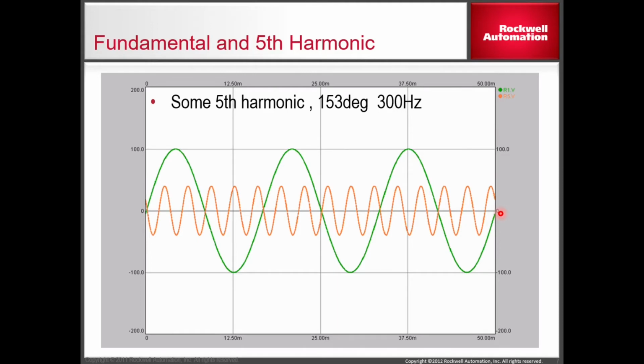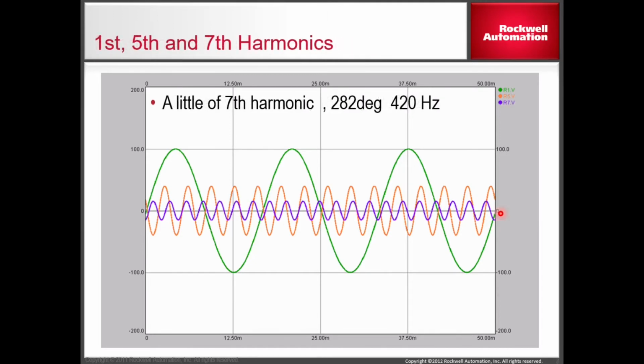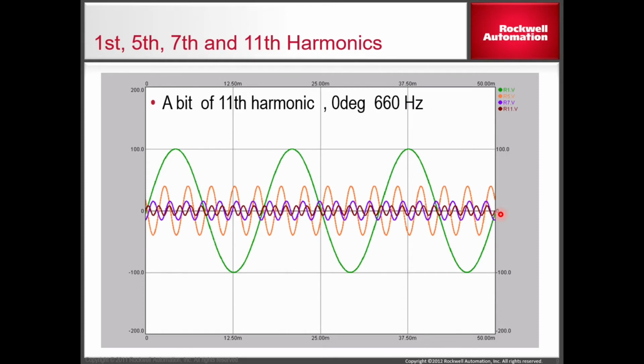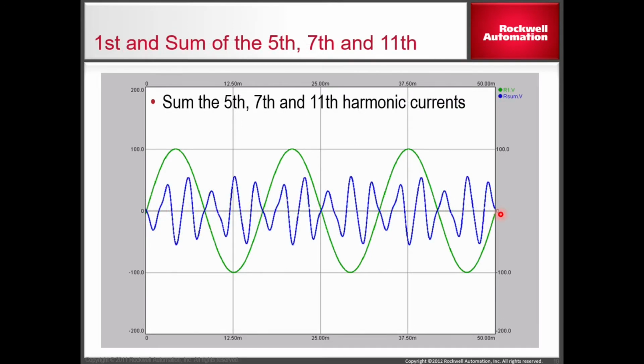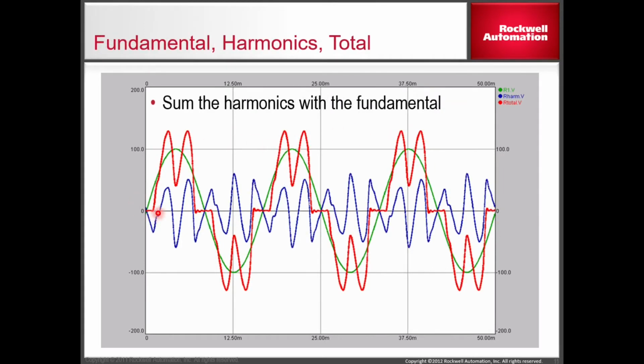Now, a harmonic is just, again, a multiple of the base frequency, 60. So times 5, this is running at 300 Hertz. The next one is going to be the seventh harmonic, which is running at 420 Hertz. And the next is the 11th harmonic, which is running at 660 Hertz. Well, when you add all these together and sum them up, what you get here is this waveform. Not the nice one we had to start with, correct?